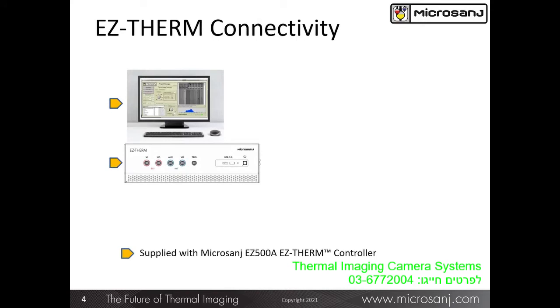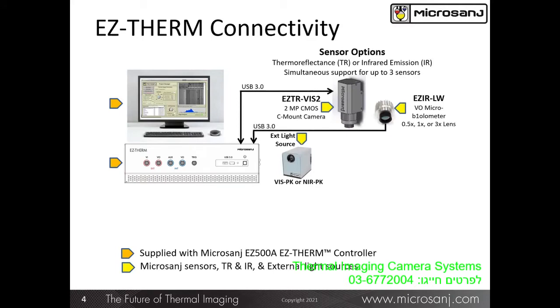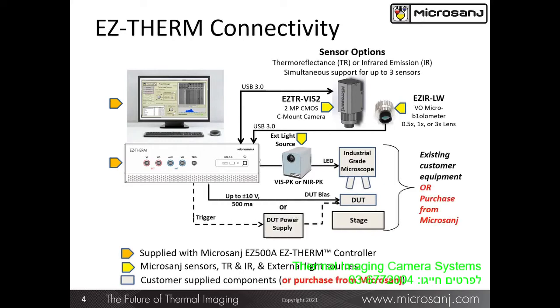As stated previously, the EZ500A platform includes a controller, display, keyboard, and mouse. In addition, we offer an external illumination pack to supplement the illumination wavelengths that are in the controller, either in the visible band or the near-infrared band, to support TR-based sensors. A number of TR or IR sensors are also available, 2 of which are shown here. The customer provides the rest of the equipment necessary to thermally analyze a sample. Connections are straightforward and intuitive. And for those customers that don't have or don't want to use their own probe station and optics, we can supply those accessories as well.